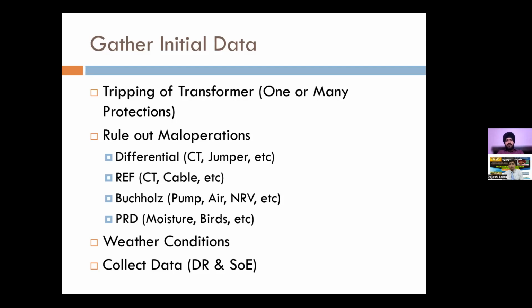Then maloperation of differential can be due to any fault which is outside our transformer. It can be a CT failure, especially on the HV side, or jumper failure, or the LA could have conducted. REF protection is a specific protection which is taken from the bushing CTs directly. In certain cases, we have also seen that REF protection operates because there is some issue in the CT circuit, or the cable has got damaged, so there is unbalanced current, and due to this unbalanced current the REF protection has operated. So first of all, you have to rule out all these maloperations. There can be many more causes of maloperations.